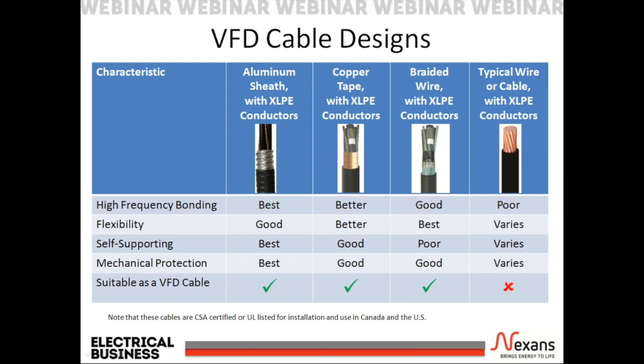For an installation that requires a cable be self-supporting, for example, installed on Unistrut, or fastened to a wall or ceiling, the aluminum sheathed cable will perform the best. The aluminum sheath is designed to be hand-trained and will retain its shape once trained into place. Note that there may be minimum distance between cable support requirements in the local electrical code. If the cable is going to be installed in an environment where it requires mechanical protection, then the aluminum sheath cable may be the answer. This could save the installer having to install a raceway, such as conduit, for cable protection.